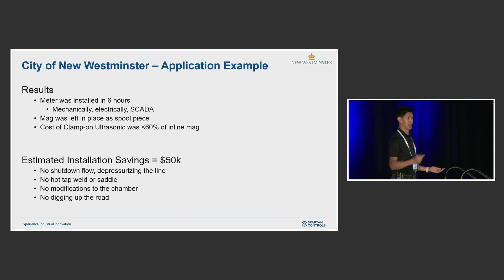The cost of the clamp-on ultrasonic was roughly less than 60% of what a new mag would be. So at the end, we estimated the cost savings were about $50,000 for that particular installation. We didn't have to shut the line down, depressurize, do any hot tap welding, modify the chamber, dig up the road, or shut the road down. We basically coned it off for a few hours, and then we were done.